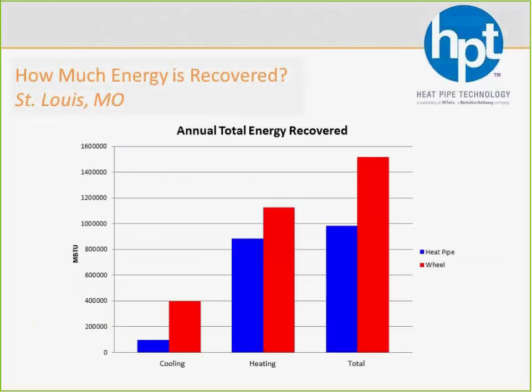So I'm just going to run a quick example. I picked St. Louis because it's kind of average when it comes to the USA environment, kind of right in the middle of the country there. If we looked at just total energy for St. Louis, Missouri over a given year, you'd find that we're recovering fewer BTUs in the summertime. Well, actually all the time, but in the cooling season the wheel is able to recover quite a bit more BTUs than we are, simply because that wheel is recovering latent heat and we're not. But you look at the heating season, again, we're both sensible devices, so we're still a little bit behind, but it's a lot closer.